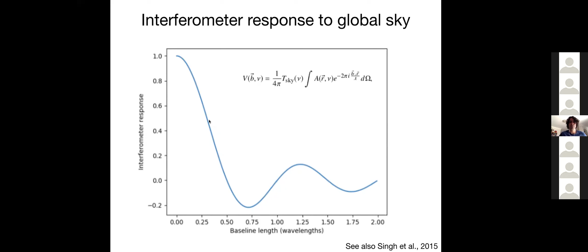And people don't normally think of an interferometer being sensitive at all to a global signal. You need fluctuations in the sky for a baseline to be able to measure anything interferometrically. But in fact, for very short baselines, there is sensitivity to a global signal. So this is what this plot here is showing. If you have baselines of less than half a wavelength, you have a really strong response here to the global signal. But most interferometers in existence don't have short enough baselines to actually measure this.